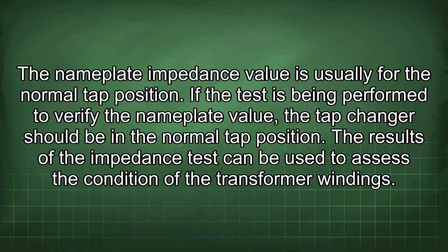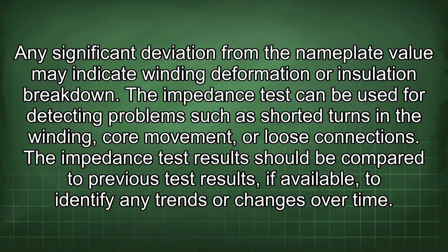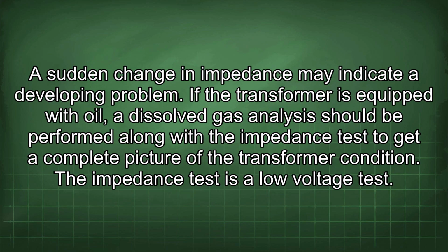position. The results of the impedance test can be used to assess the condition of the transformer windings. Any significant deviation from the nameplate value may indicate winding deformation or insulation breakdown. The impedance test can be used for detecting problems such as shorted turns in the winding, core movement, or loose connections. The impedance test results should be compared to previous test results, if available, to identify any trends or changes over time. A sudden change in impedance may indicate a developing problem.